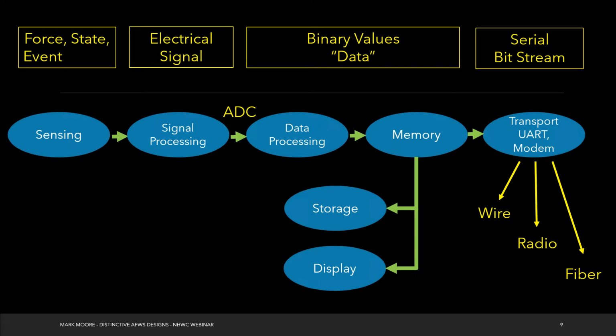And you might be sitting there thinking, all right, Mark, that's great, but we have SDI-12 PTs. We're not worried about 0 to 5 volts or 4 to 20 milliamps. This is still the same process that occurs with an SDI-12 PT, where it's putting out a digital output. What's happening is that all of this sensing, signal processing, and data processing is happening in the PT itself. And so you still want to calibrate those devices because you still have the same things going on. Some of it's just behind the scenes.